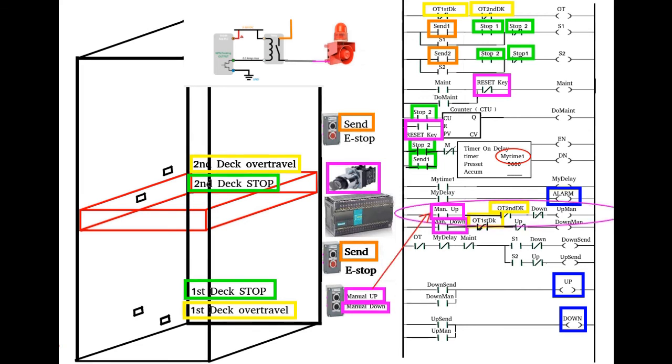Notice that the manual up only has 2 restrictions. The platform cannot be stacked all the way up and it cannot be going down. Otherwise, pressing the manual up, it will close the associated virtual contact, energizing the up man coil, and this coil will close its associated normally open contact, energizing in this case the down command. And yes, I got those 2 backwards. I just went ahead and fixed it.